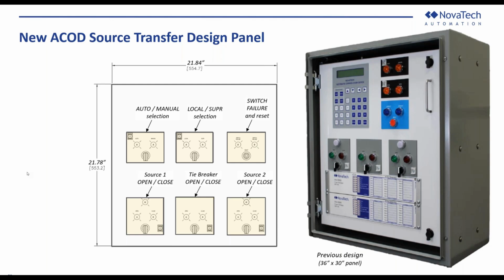24 inch enclosure. On that control panel, looking at the updated design on the left, top left, we have the auto manual control and indicator lights. This allows you to enable and disable the ACOD logic for running. Next to that, we've got the local supervisory control and lights to enable or lock out remote operation of the ACOD. That way it can be worked safely by a local technician.